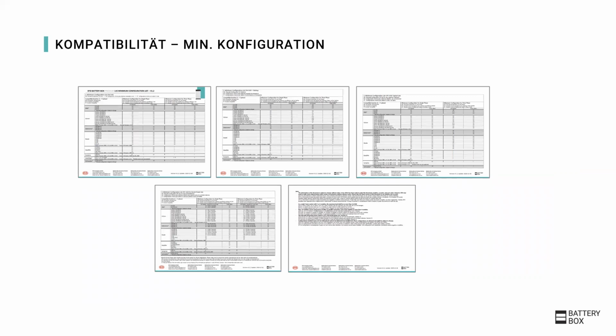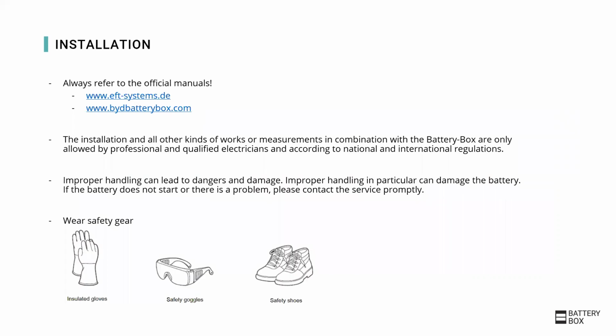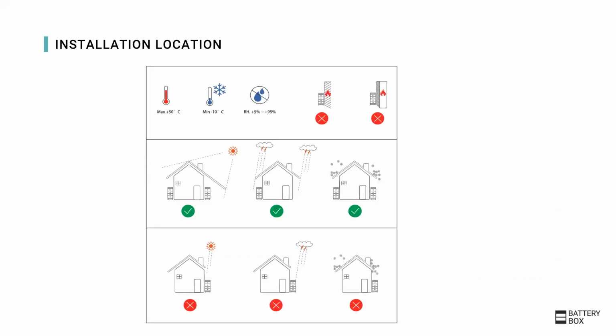To check which configurations are possible for which inverter and for which kind of use, please again refer to the latest minimum configuration list available online. As mentioned before, please refer to the manual for the installation and regard the safety instructions. The Battery Box Premium HVS, HVM, and LVS have the same protection rating of IP55. Therefore, the requirements on the installation location are exactly the same as already described for the Premium HVS and HVM. The temperature range is again from -10 degrees to +50 degrees Celsius. The power will be limited below 5 degrees.